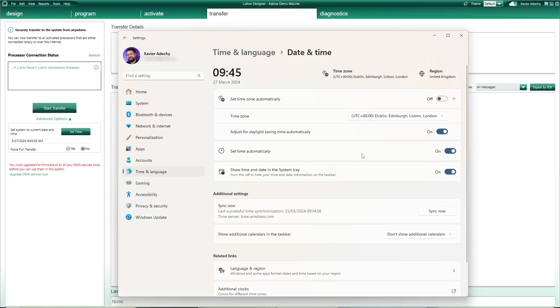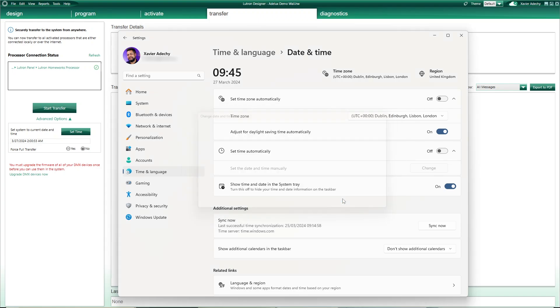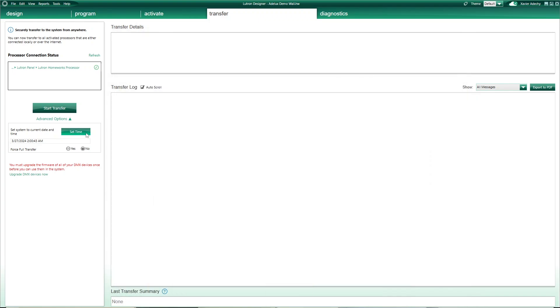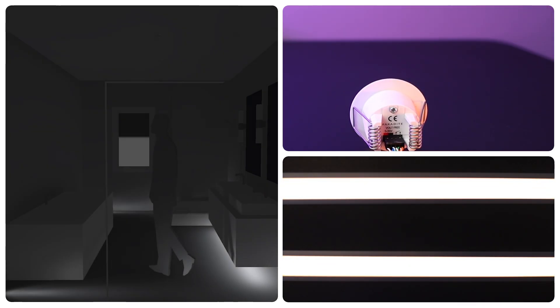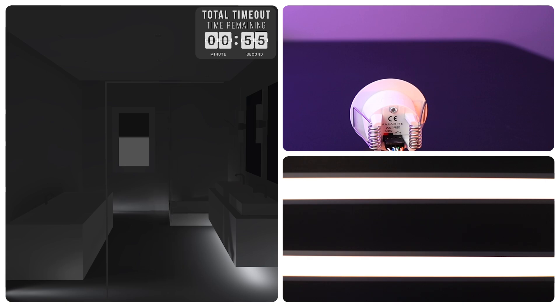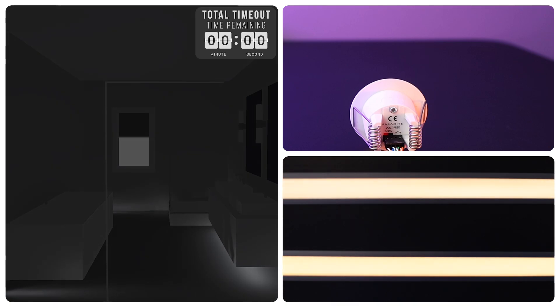Now, same thing: I change the time on my computer to 2 a.m. again. Back on the Transfer tab, I click on the Set Time button to update the time on my Homeworks processor. As it is night time now, when I walk in the bathroom, lights turn on to a low level as set in my Bath Night On action in the Occupancy tab. And when I exit the bathroom, my shorter timeout kicks in, and after just 1 minute my lights go off.